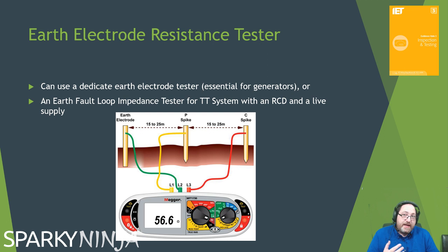We have the dedicated earth electrode resistance tester, which comes in a few types. There's 4-stage, 3-stage, and there's also a stakeless type. Or, for testing electrodes, we can use an earth fault loop impedance tester if it's a TT system with an RCD on a live supply.